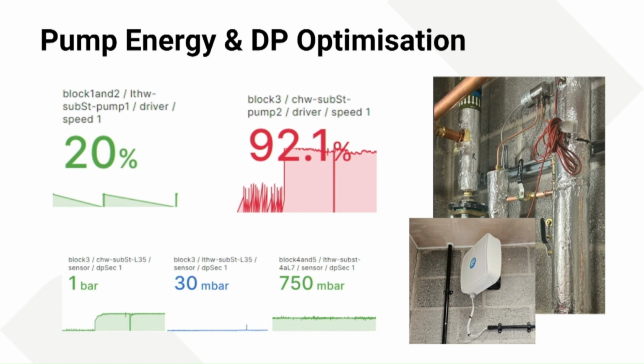These pumps can be running at 11 kilowatts - that's £20,000 of energy a year per pump. If you knock that speed down by changing DP settings, you can get some instant savings. The payback on optimization works from day one - you can get ahead of the game, your savings are straight away outstripping the costs.